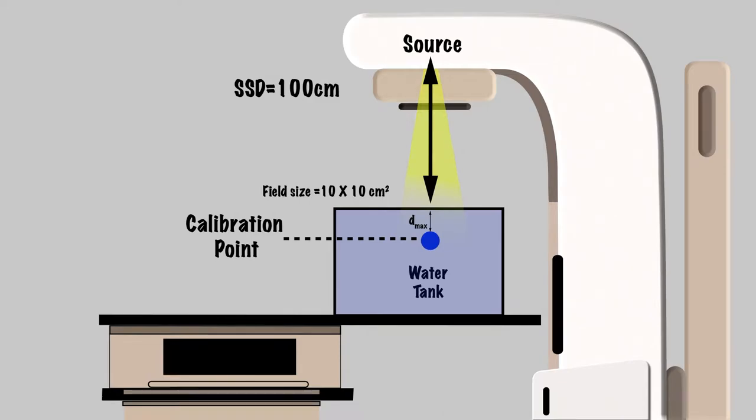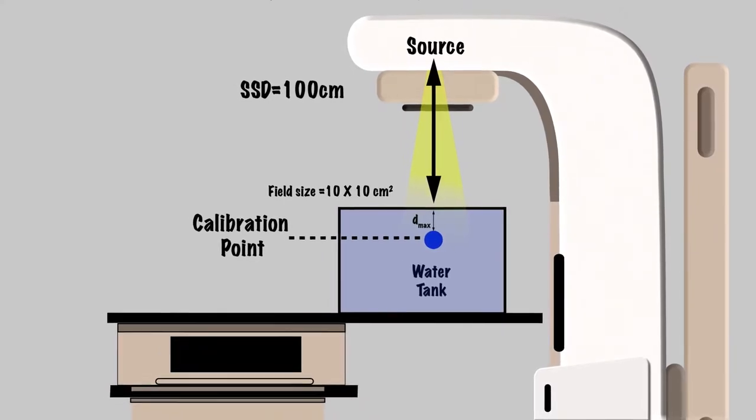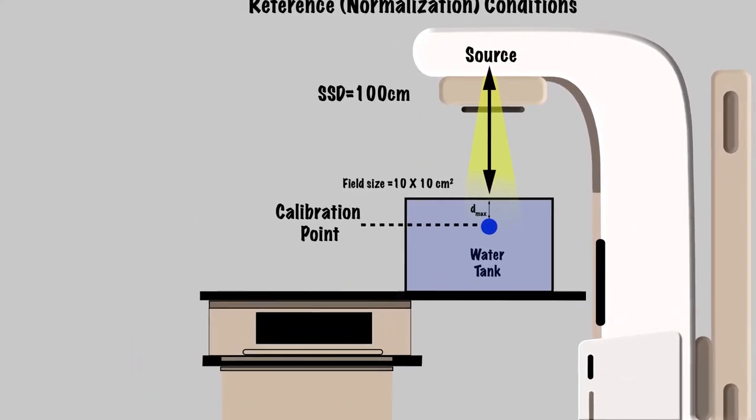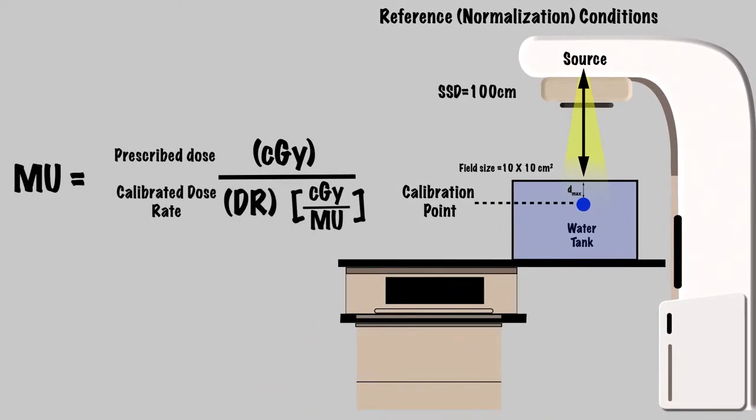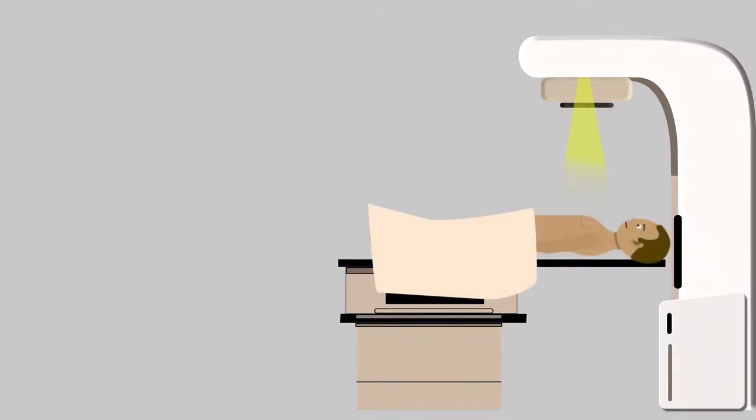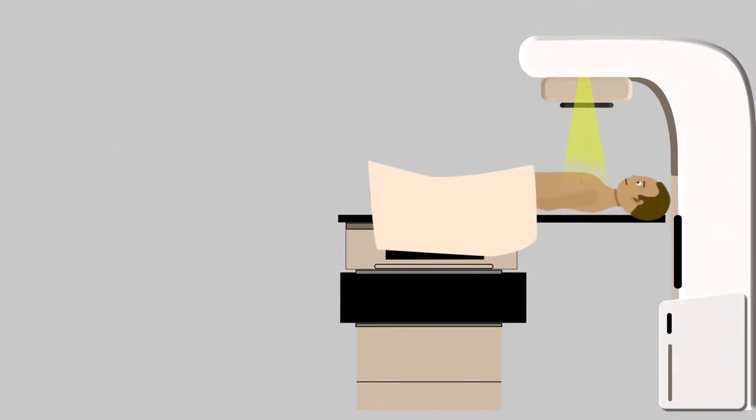If we were prescribing the dose to the calibration point under this setup, the number of monitor units would just equal the dose in centigray. In this case, our formula would simply be prescribed dose over calibrated dose rate. However, since our treatment conditions are usually different than the reference conditions, we must account for these changes.